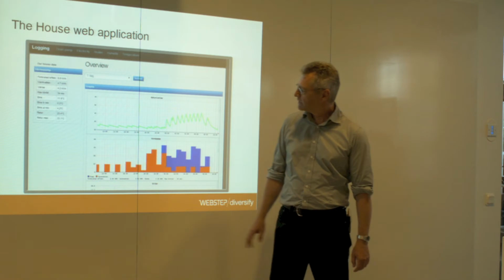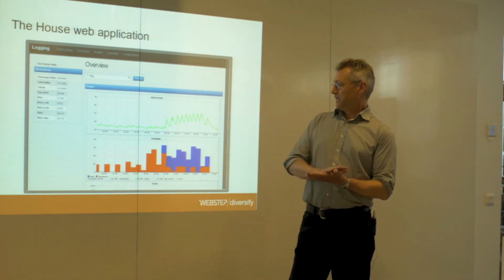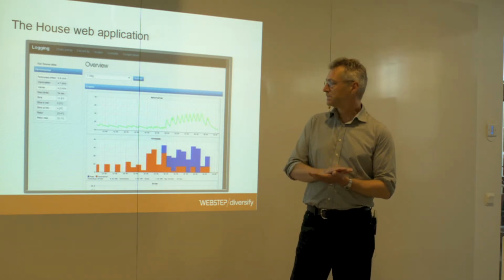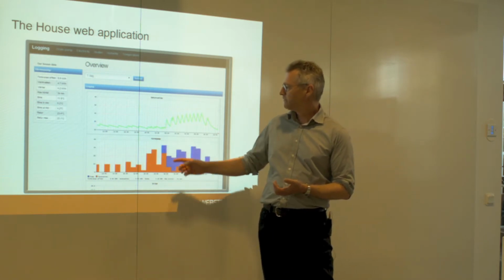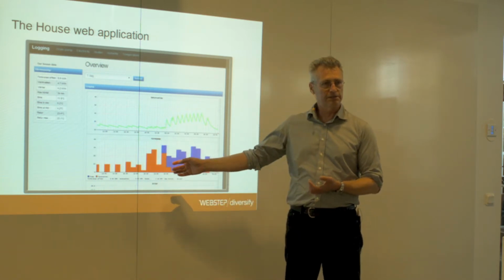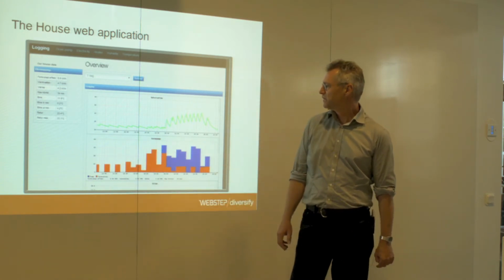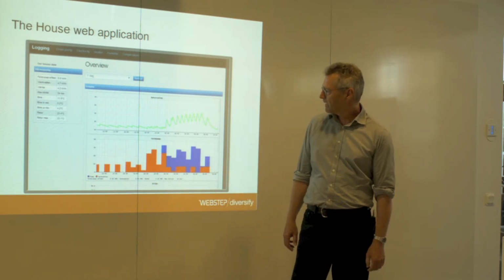And what I've done here, I have two data sources. One is the runtime for the hot water production, and the other one is the runtime for the pump itself. Then I take the pump itself minus the hot water production, and then I get the red ones here, which are for the hot water, and this one here is when it heats as well.